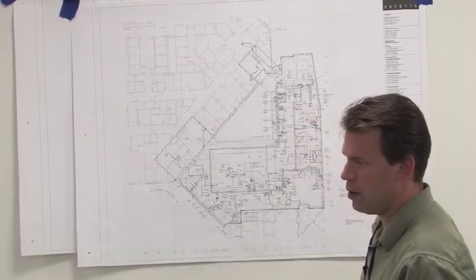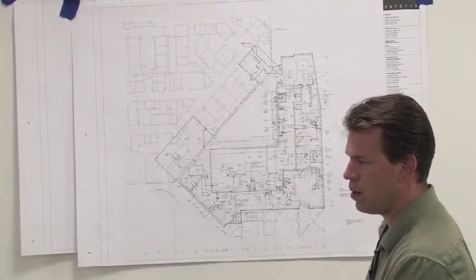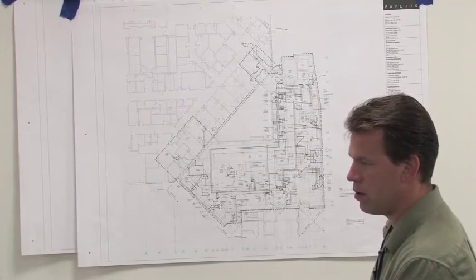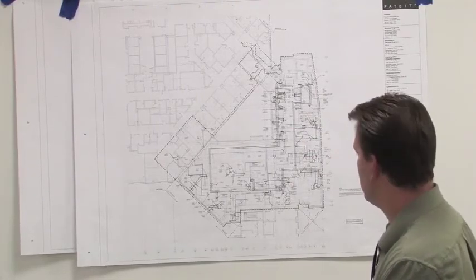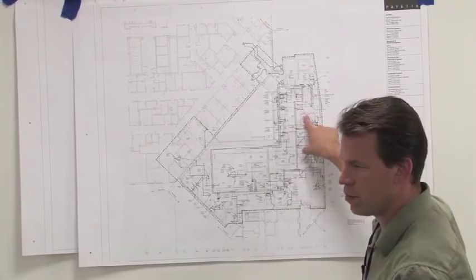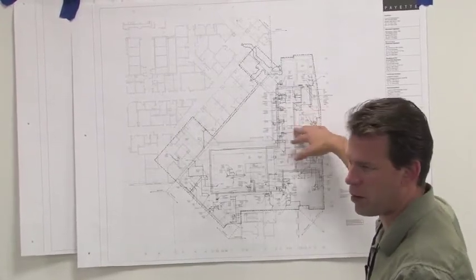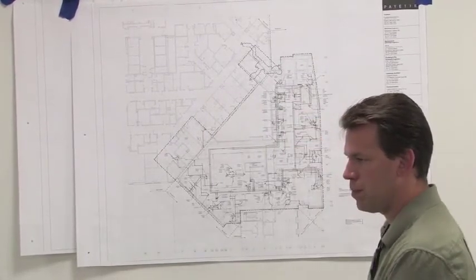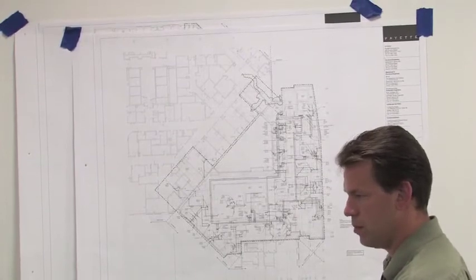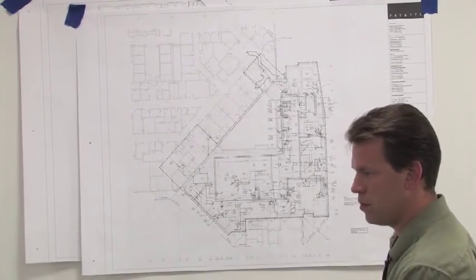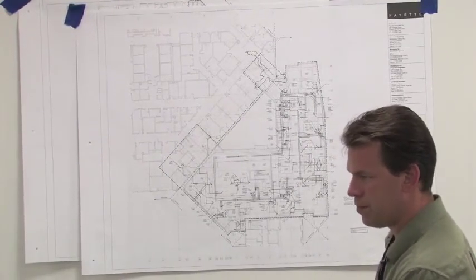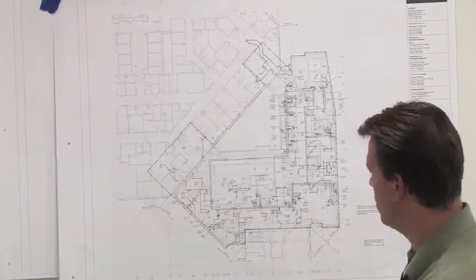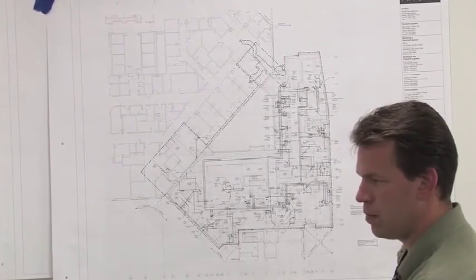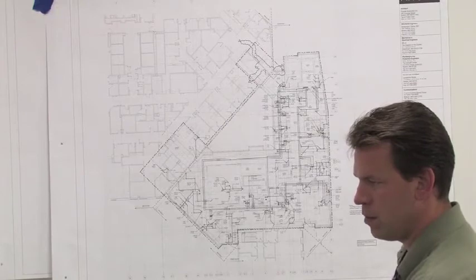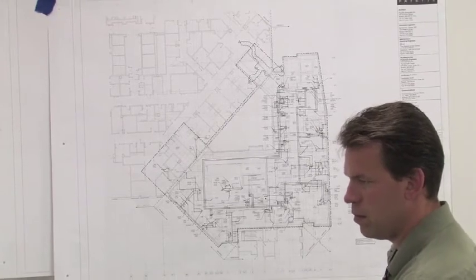So what do they do, just put the dry system and draw a pipe down? It's on the same system? Yeah, it's a branch off of the system. Just a branch line off it, with detectors as well. So they put electrical detectors in there, and then they put the dry system in. They kind of mirror image it, but it all comes off that one. If you get water in one, you'll probably get water in the other, depending on where the air is coming out. It'll be air in the whole system. Right.